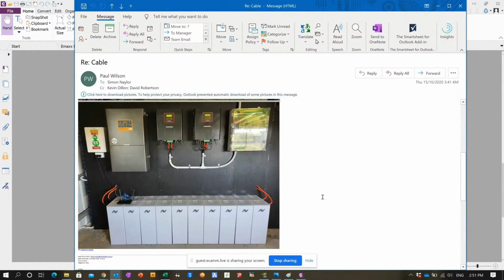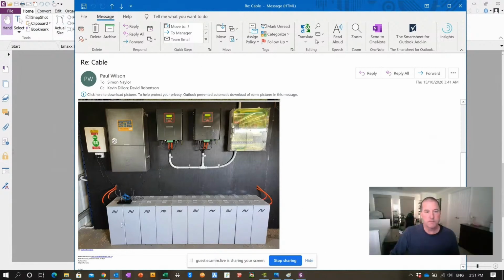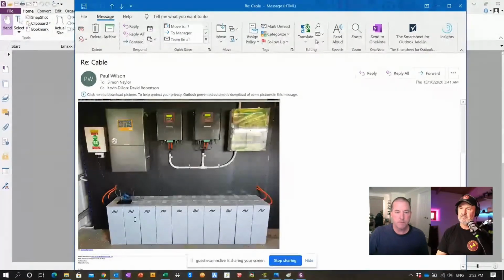There we go, okay, this was just recently commissioned. This is 20 by 2.2 kilowatt hour modules, and each of these is 13.8 volt DC. You can see there's 10 in a row, so 10 by 13.8 is 138 volts, and that's the second row behind. So here we have 44 kilowatt hours of storage, sits on the floor, connects up to a DC MCCB here.